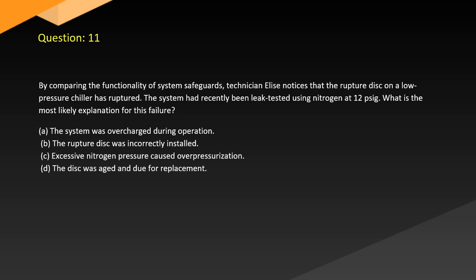Question 11. By comparing the functionality of system safeguards, technician Elise notices that the rupture disc on a low-pressure chiller has ruptured. The system had recently been leak tested using nitrogen at 12 psig. What is the most likely explanation for this failure? A. The system was overcharged during operation. B. The rupture disc was incorrectly installed. C. Excessive nitrogen pressure caused overpressurization. D. The disc was aged and due for replacement.